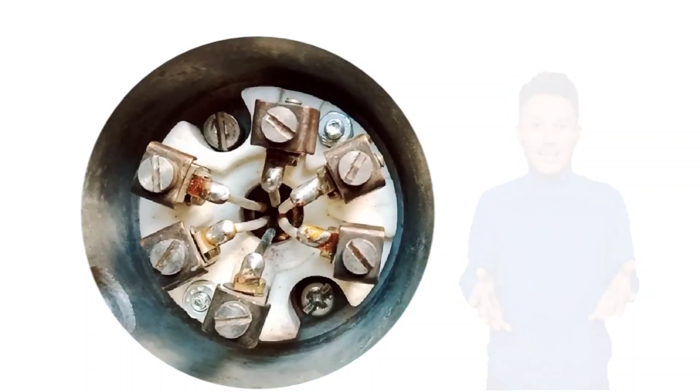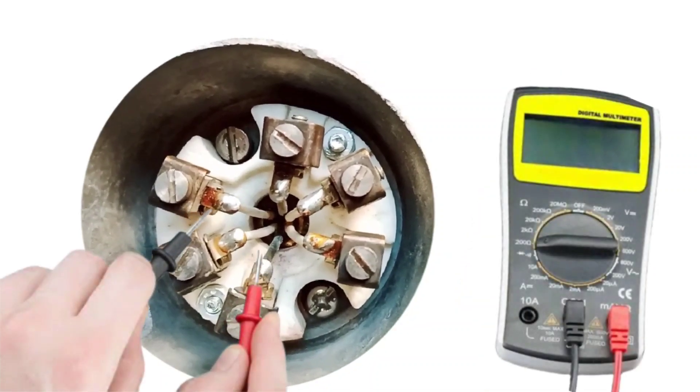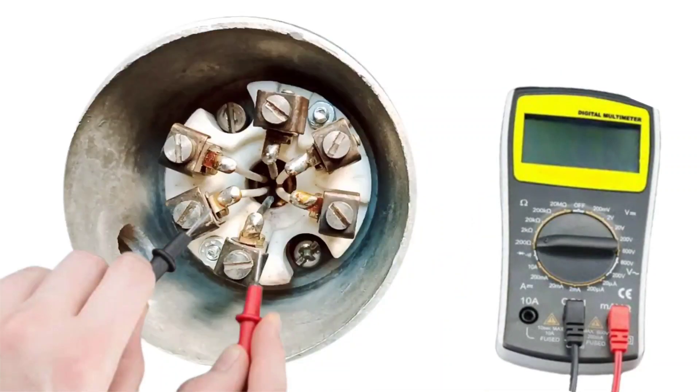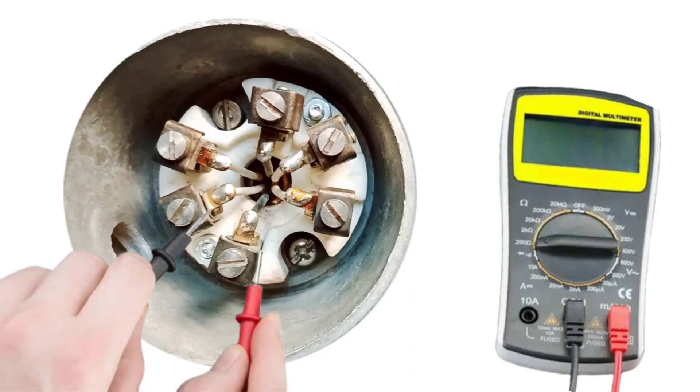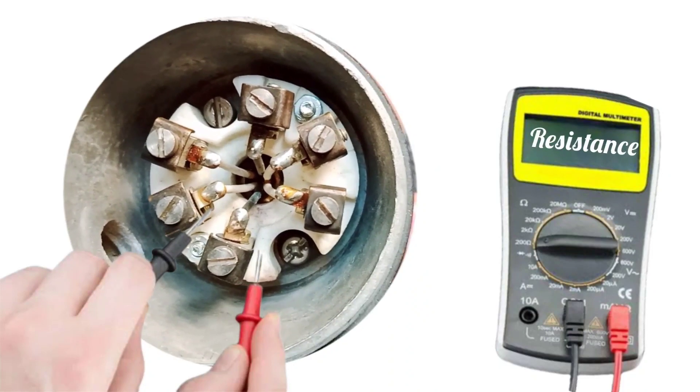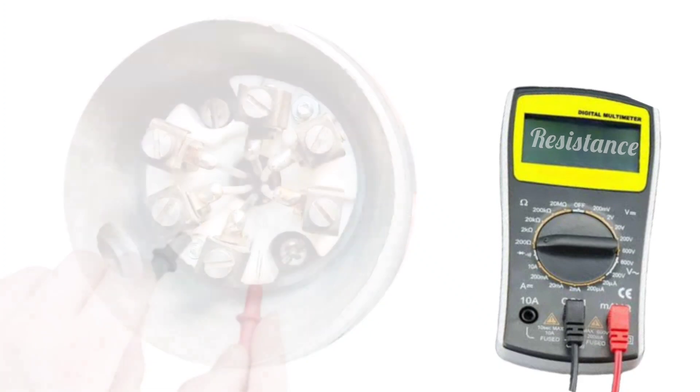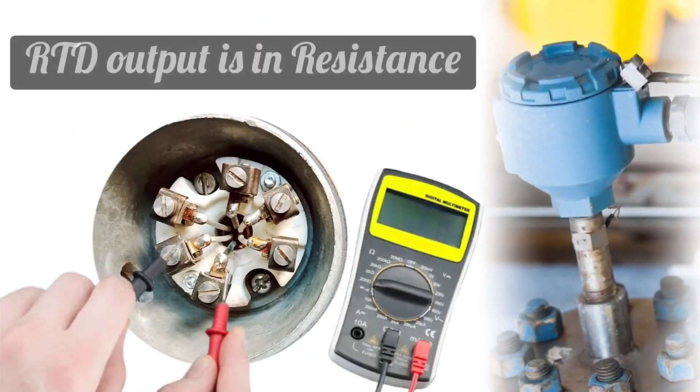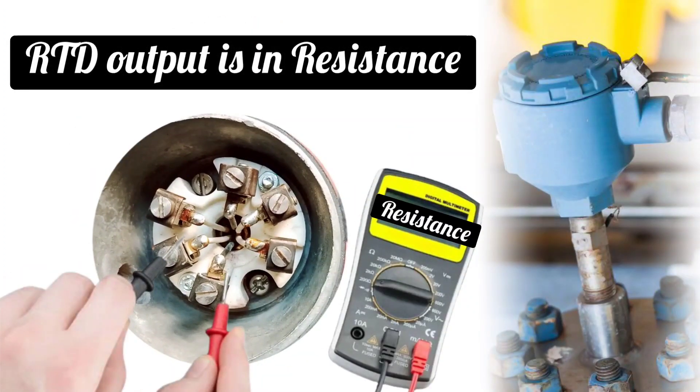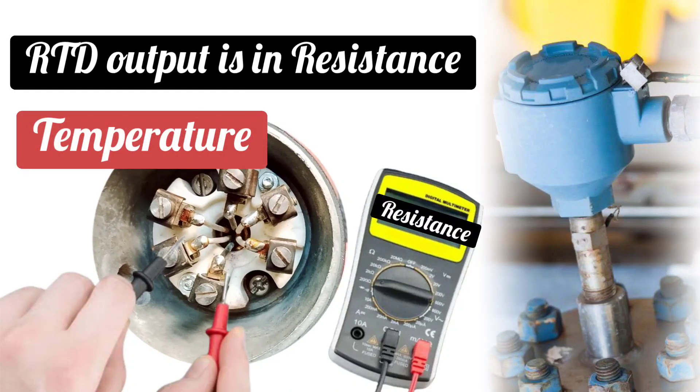One knob of multimeter is put at white color wire, and another one is put at black color wire, and we will check the resistance. RTD's output is resistance, and from this resistance, temperature is calculated.